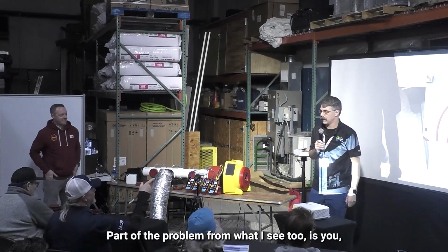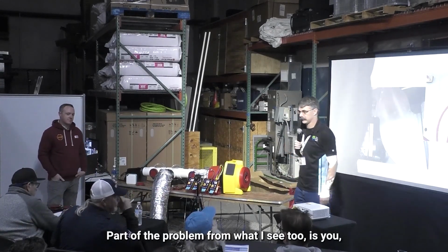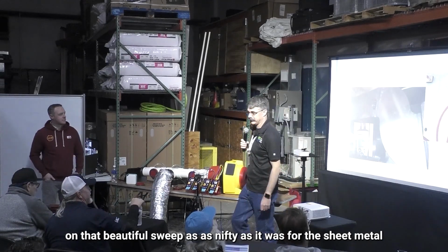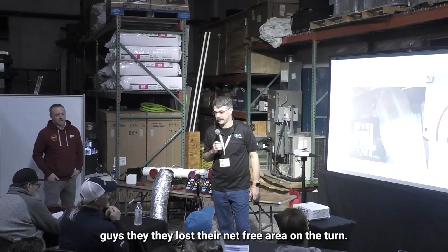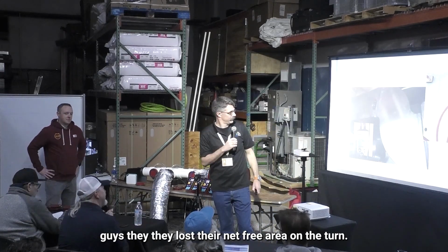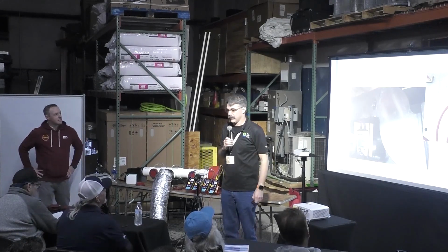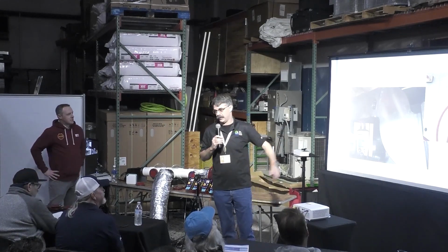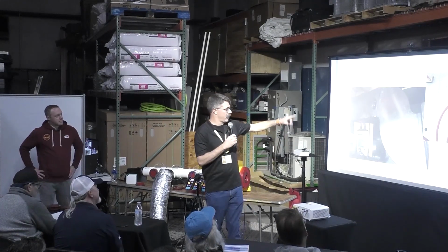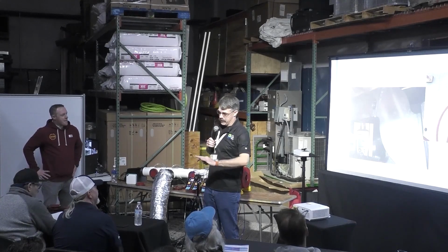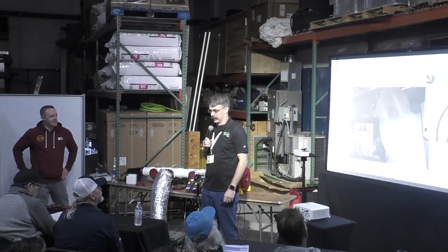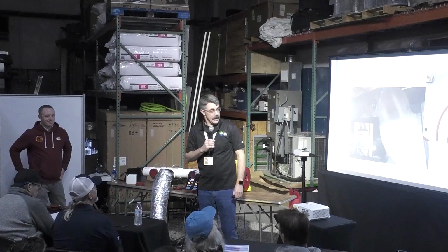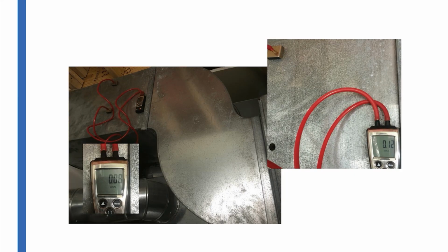One of the problems from what I see too is, well, there's many problems with that. But yes, John's saying they lost their net free area on the turn. There's many problems with that duct fitting when you start looking at it. I mean, it looks pretty from an aesthetics point of view.